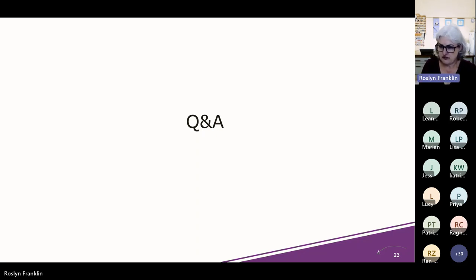One question: is it required that if processing porous loads, the Bowie-Dick test is done that day, but the Helix test is done daily regardless? That's pretty much the question I've just answered - in my view, from what I've read and understand, you could run a Bowie-Dick and a Helix test, but they need to be done at separate times. My understanding is the Helix is the more challenging load. I'd be interested to know what porous items practices are putting through, because it's generally more cost effective to use single-use items for gowns, sterile gauze and similar things - though that's a decision each practice makes.